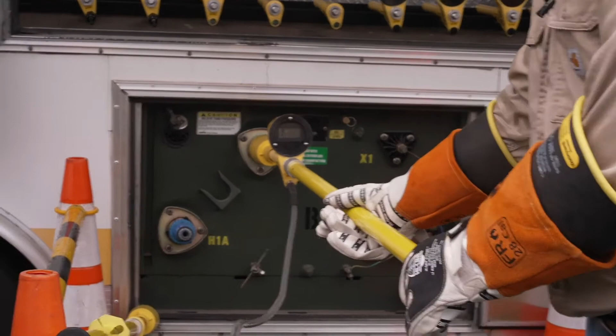Again, we'll go phase to ground first for the same two reasons. You want to verify the tool's working on the live node voltage source, and you also want to tell your partner, hey, we're mutually accountable, ready for the job. So here we see a 1. That 1 is just giving us a funky reading on the device. It's telling us you've got the tool in the wrong setting. I've still got it in the 2 kV setting. I'm going to flip it to the 25 kV setting. Since these numbers are a little high, it may still peg the device. So we see about 20,000 volts.